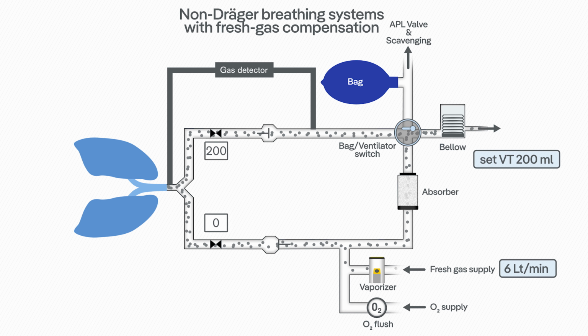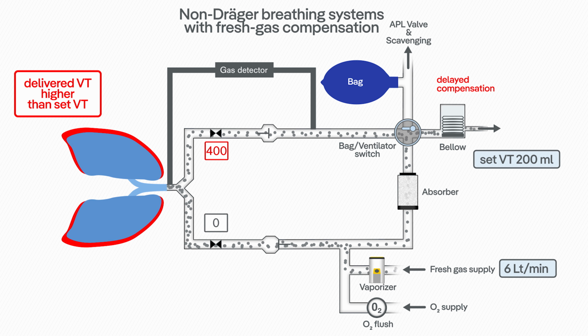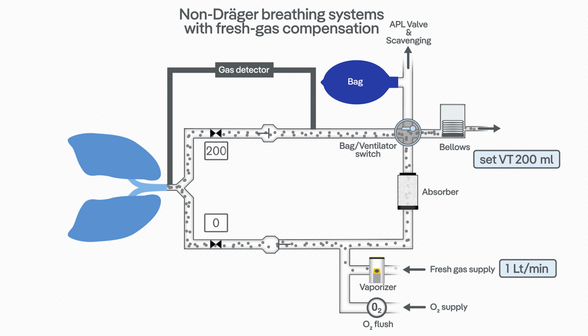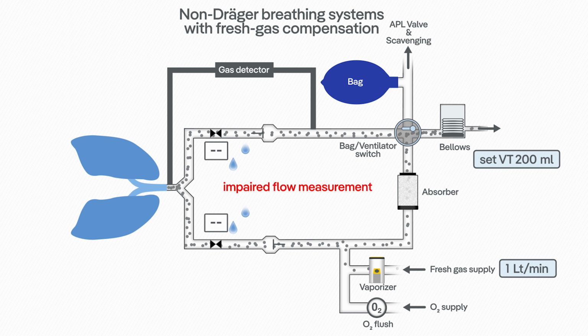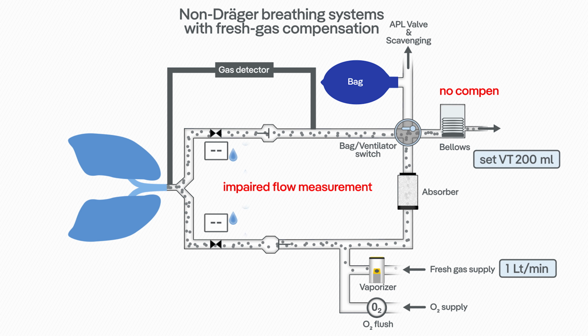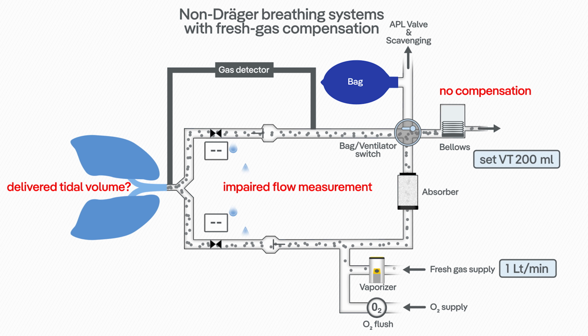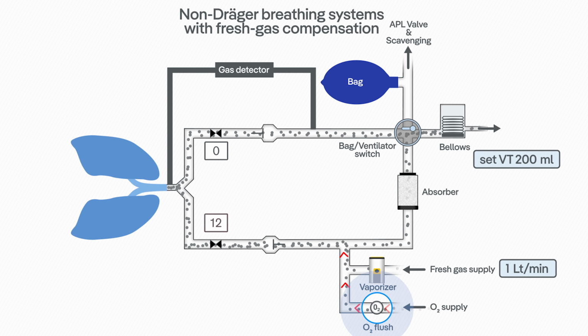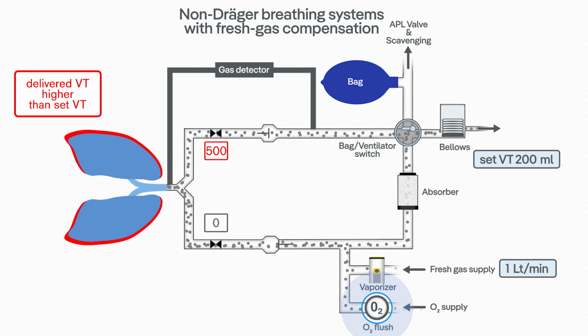Additionally, if rapid changes in fresh gas settings are made, the system latency causes a delayed compensation of tidal volume. This may result in tidal volume and inspiratory pressure peaks. Moreover, this function depends on the proper functionality and precise measurement of the flow sensors. In case of flow sensor failure or impaired measurement due to condensation, the fresh gas compensation will fail. Also, every time when oxygen flush is used, this will influence the delivered tidal volume.